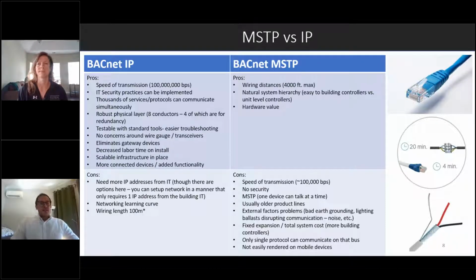Speed of communication is becoming ever more essential with a BAS system. You're starting to have a lot more data needing to be moved around within that system. It's no longer just HVAC, so you want higher speeds of communication. The difference is pretty substantial: you have 100 million bits per second versus about 100,000 bits per second, comparing IP versus MSTP. The next very big difference comes down to IT security practices.